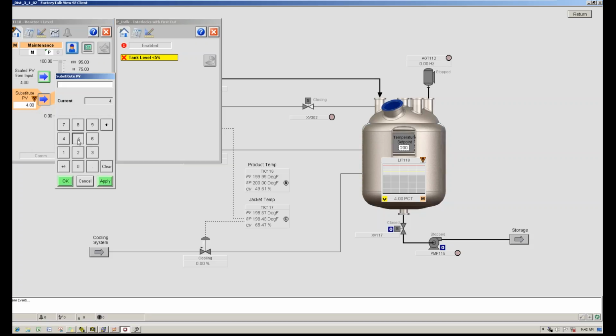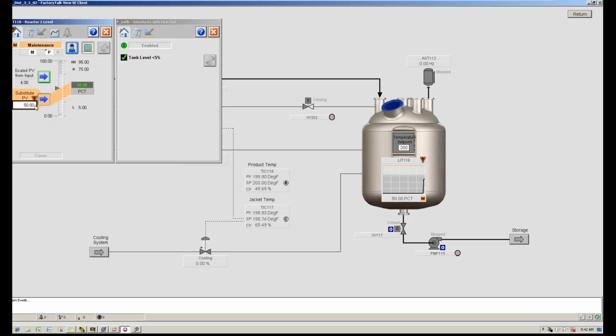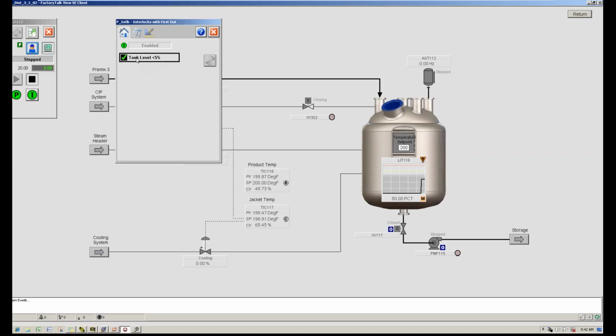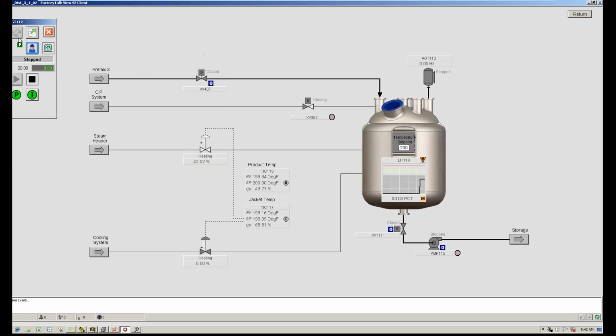I know that I've got 50% tank level in there and I need to agitate that product. I can use this substitute value of 50%. You can see straight away my tank level now is satisfied. My agitator interlock is green, and if I was to put it into operator mode, I can now operate that agitator. So that just gives you a brief introduction into the power and the capability of the library and the faceplates in terms of troubleshooting and fault finding on the system.